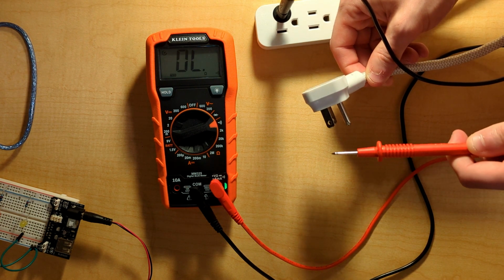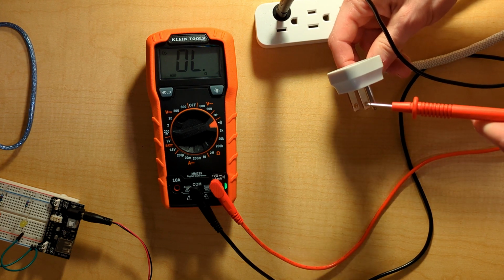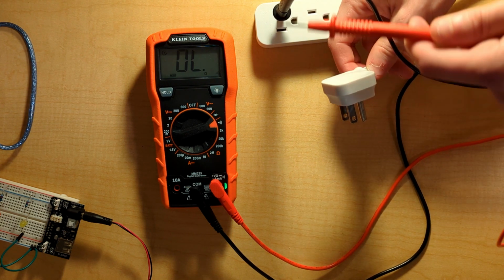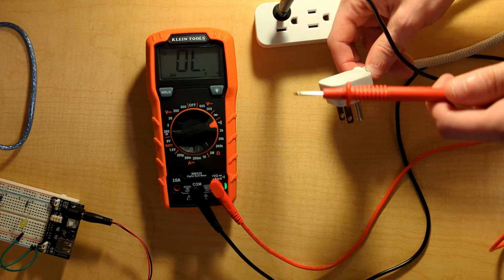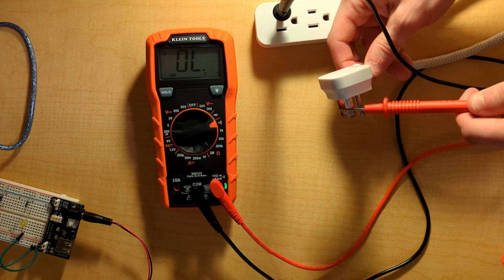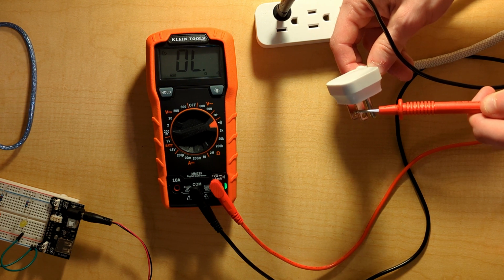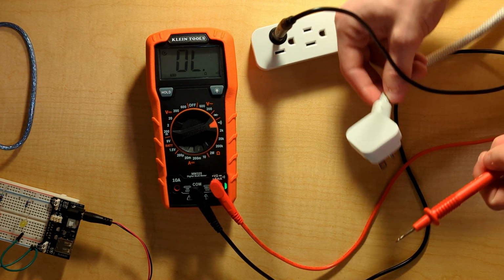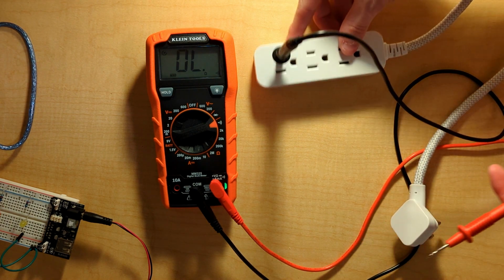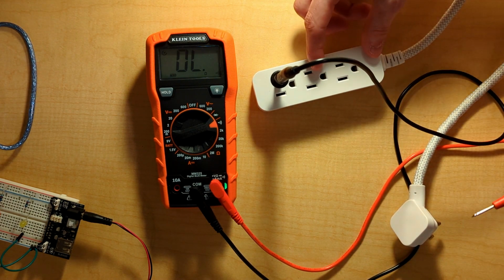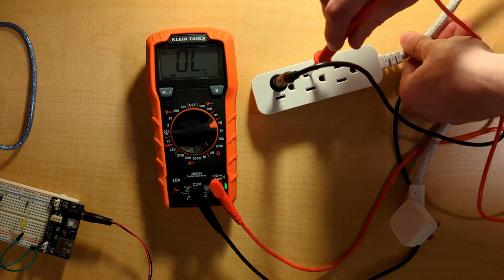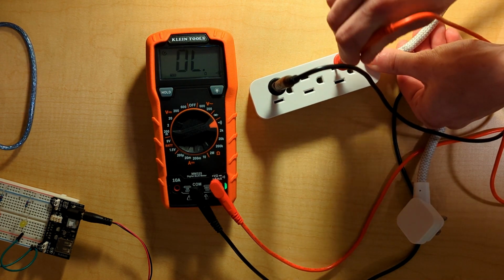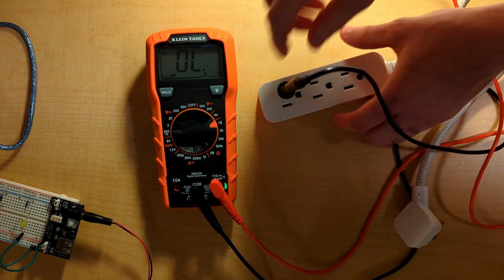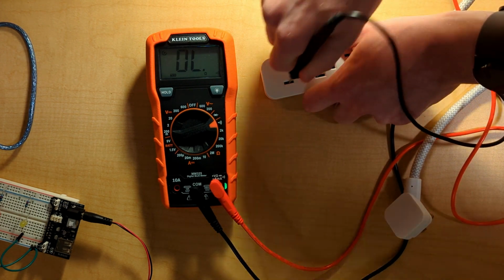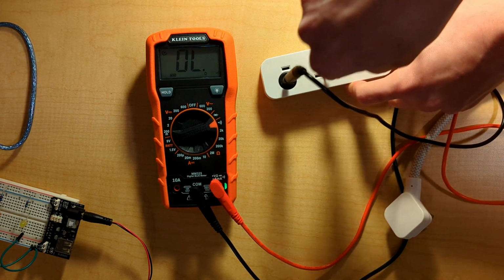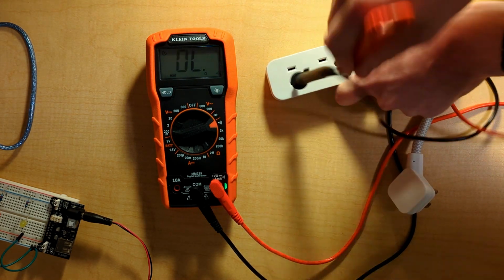To check for any shorts between any of the wires, I'm going to touch the other end of the probe to the neutral side while this probe is connected to the hot side, and I shouldn't get any kind of reading between them. And you'll see we still have an open line, meaning that there's no shorts between these wires. We can also do a continuity test between each of these outlets on the extension cord. If I go between the hots on each of these ports, you'll see they're connected. We can do the same with the neutrals. And you'll see they are each connected.